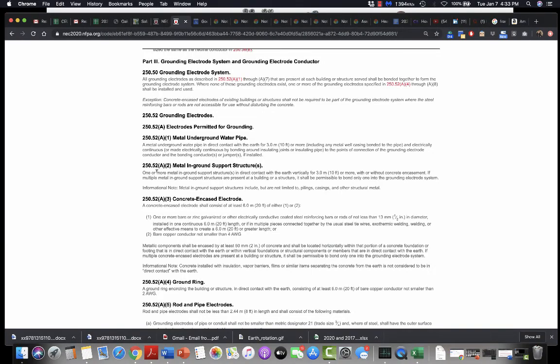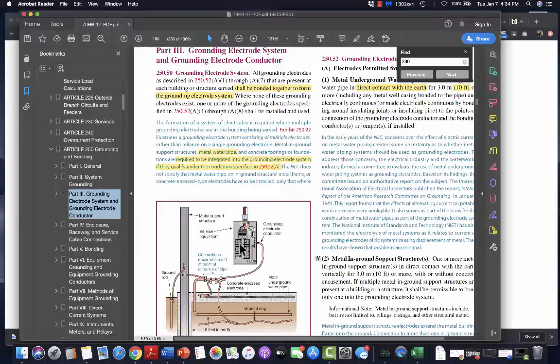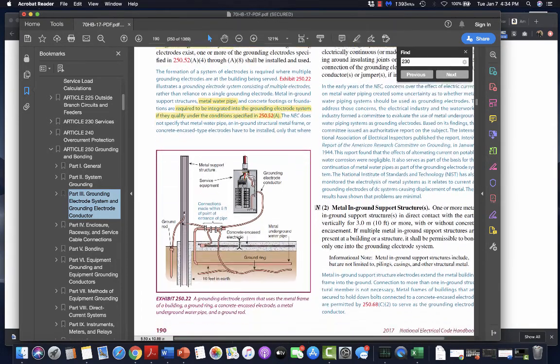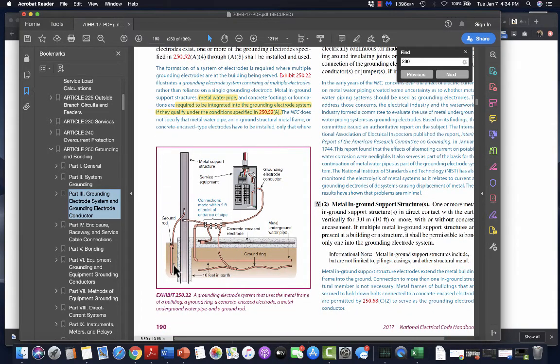So here we are. Part 3, Article 250, Grounding Electrode System and Grounding Electrode Conductor, 250.50, Grounding Electrode System, 250.52, Grounding Electrodes. And here's what it looks like in the 2017 NEC. Darn, they have nice pictures. Pretty much the same thing. So we can see there's a ground rod, there's a ground ring, there's a concrete encased electrode, electrodes all over the place, even a metal underground water pipe.